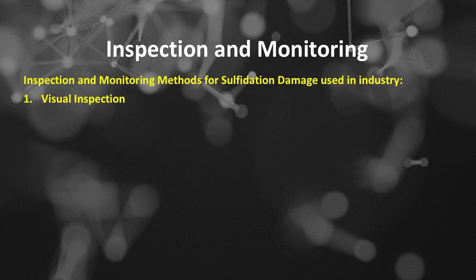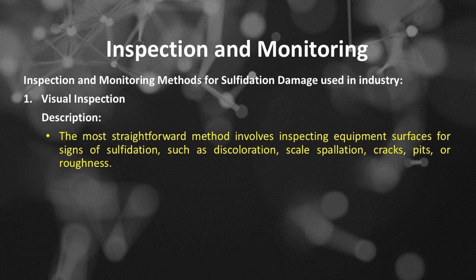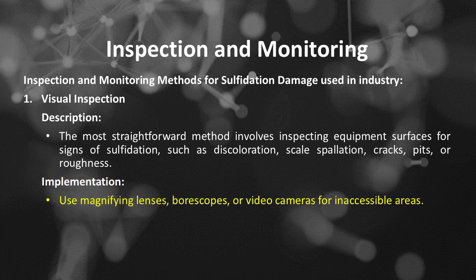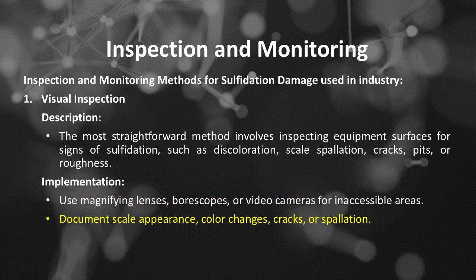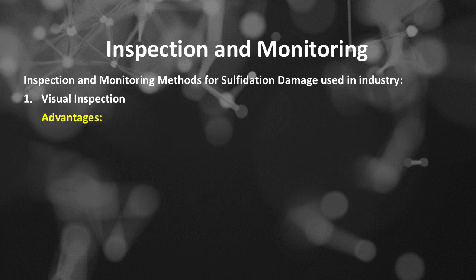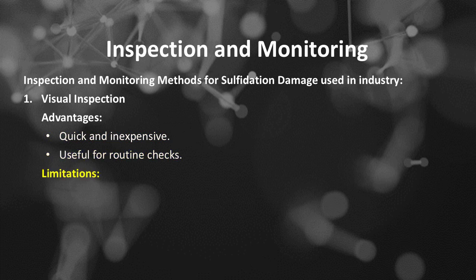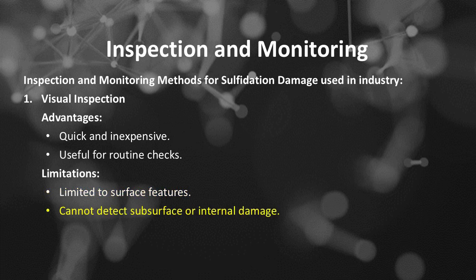Number 1 of the inspection and monitoring methods for sulfidation damage used in industry is visual inspection. Description: the most straightforward method involves inspecting equipment surfaces for signs of sulfidation, such as discoloration, scale spallation, cracks, pits, or roughness. Implementation: use magnifying lenses, borescopes, or video cameras for inaccessible areas, and document scale appearance, color changes, cracks, or spallation. Advantages: quick and inexpensive, and useful for routine checks. Limitations: limited to surface features, and it cannot detect subsurface or internal damage.